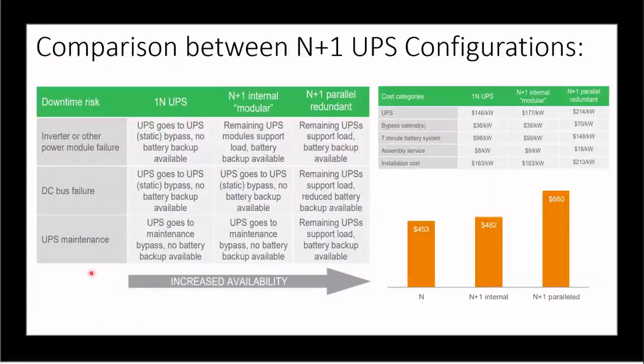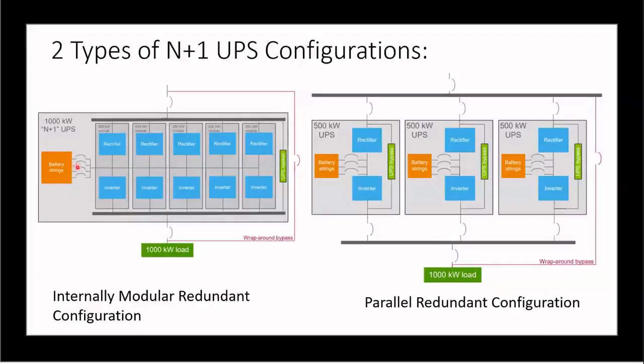If there is a DC bus failure, the DC bus is this, right? So if there is a failure, here it is a single point of failure. On this side, if the DC bus goes off, then we have to close this UPS unit, and then power will flow through the static bypass. And here, if one of the DC links goes off, there is a very low possibility that the DC links of all the UPSs will go off, right? So if this one goes off, we still have the other UPSs supporting the load. That is the advantage here.